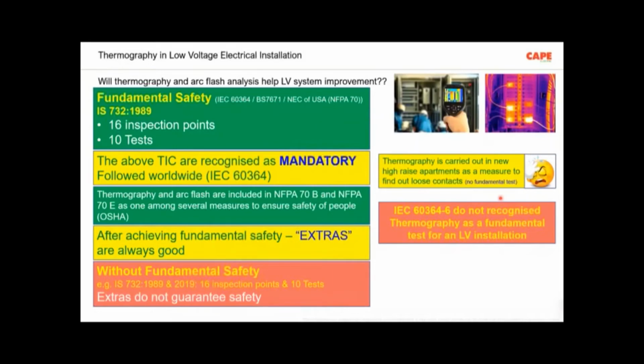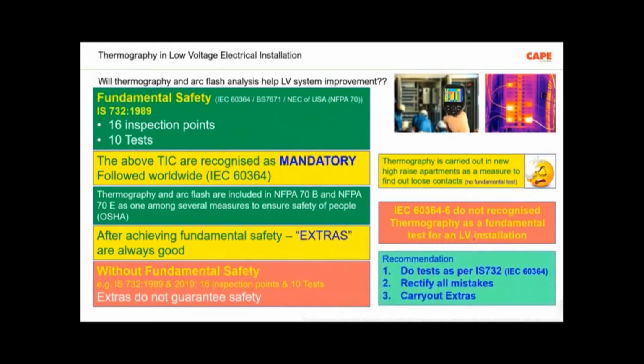So as a result, the statement which I made last time is that IEC 60364 or our Indian standard, the IS732, do not recognize thermography as a fundamental test in an LV, low voltage electrical installation. So inside a building, inside an electrical installation, thermography is not recognized as a fundamental safety requirement. If you have fulfilled the fundamental requirement, you can do it extra.